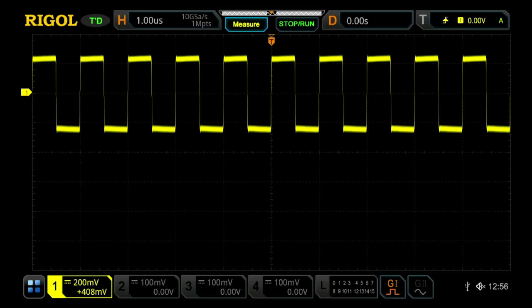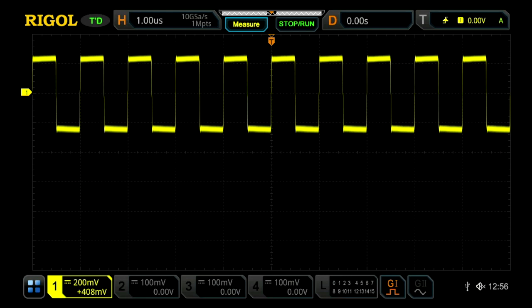These instruments all come equipped with an FFT spectrum display mode, which allows you to easily view a signal not only in a time domain, being shown here normally in yellow, but also in a frequency domain. In order to access this, you can do this through the quick touch menu at the bottom by pressing that and then FFT.